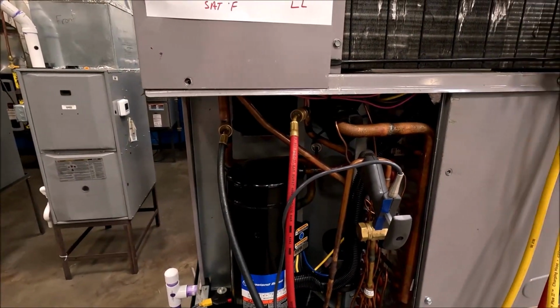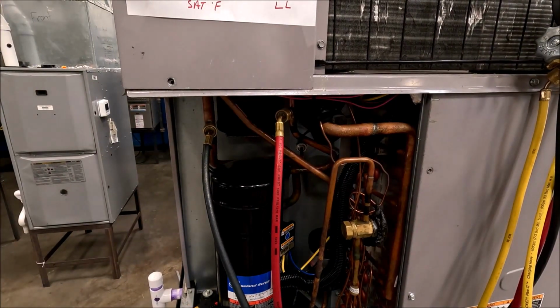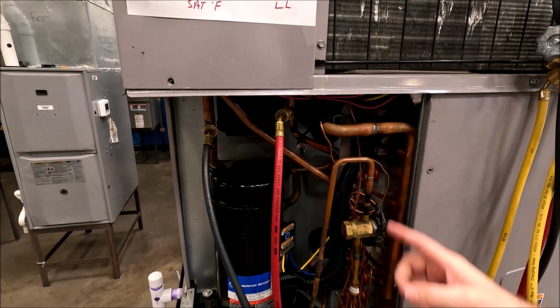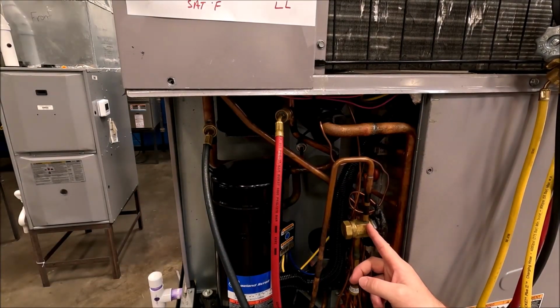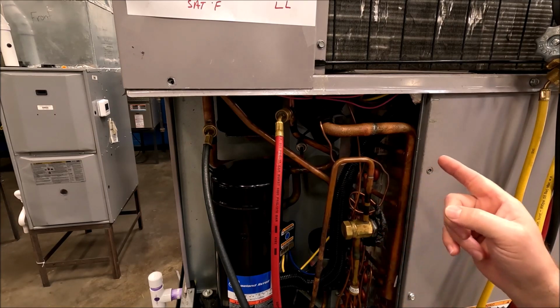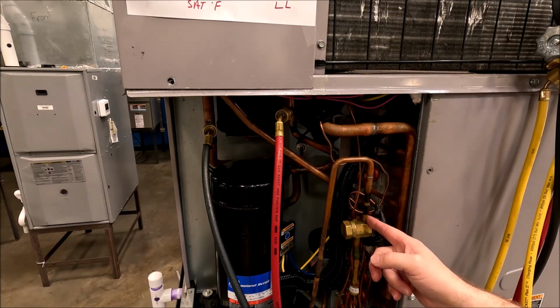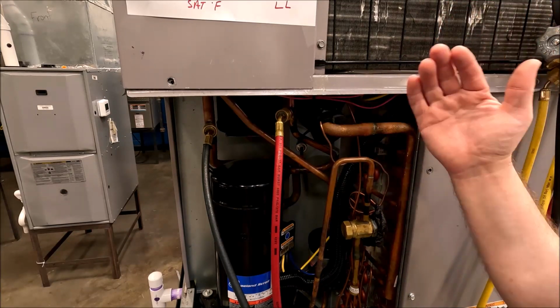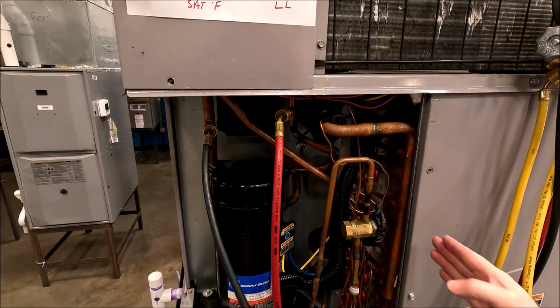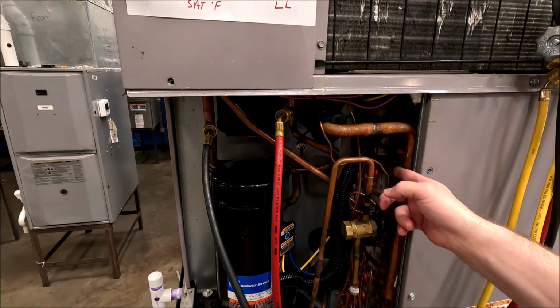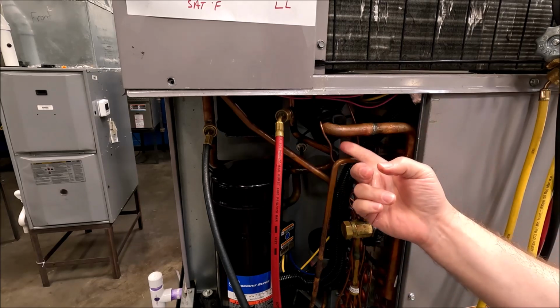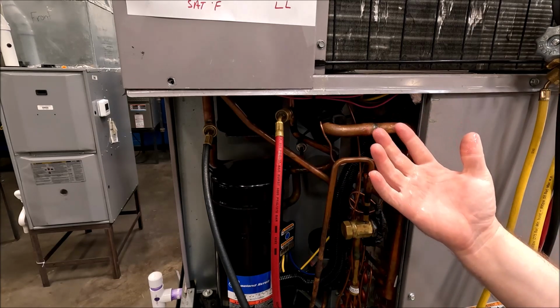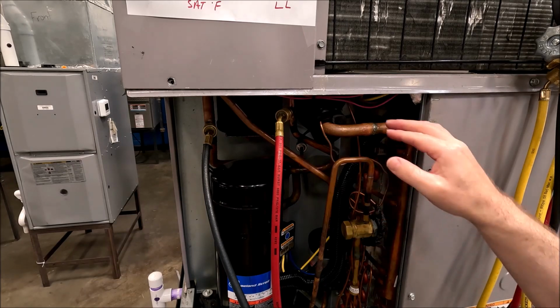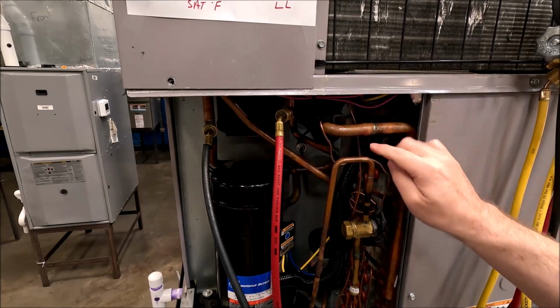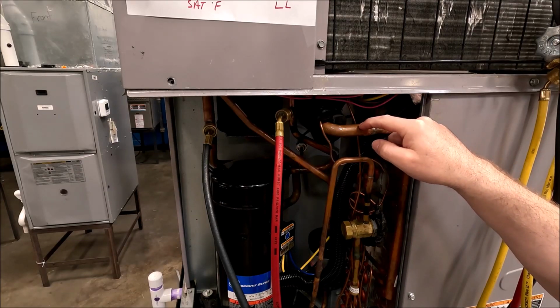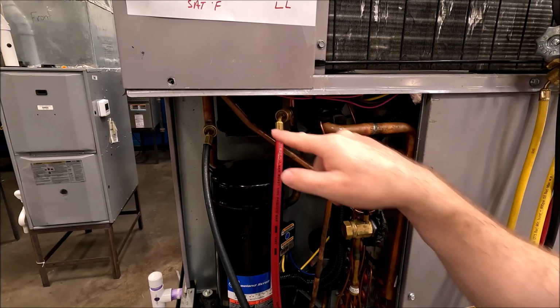You've got to know where to get your superheat subcool stuff. So if you can identify, all right, find that metering device. It may be a piston. In our case, it's a TXV. So I know that liquid line ends at that metering device. And I know it came from my condenser where I rejected heat and it should be liquid, okay? Another thing, usually right here by this blower compartment, you're going to see the vapor line, okay? Besides that, the TXV bulb is strapped right here. If it came from the factory, it's probably in the right spot. You never know what you get sometimes in the field, but that vapor line being right here would be an acceptable spot. It's only a couple feet further to the pressure tap.